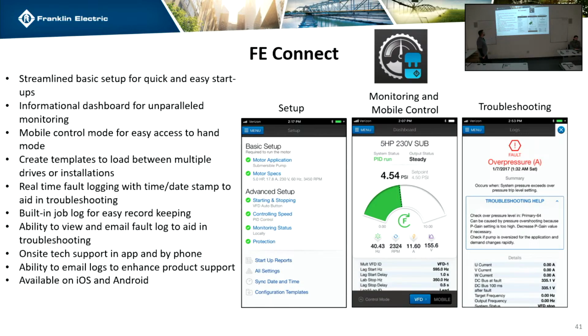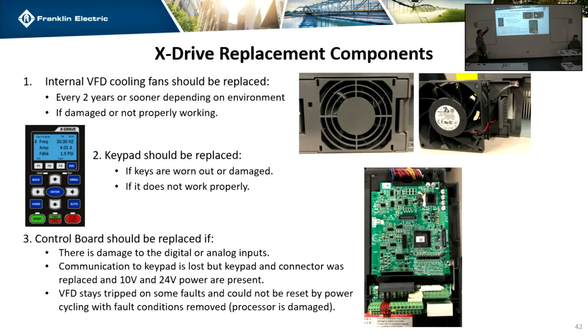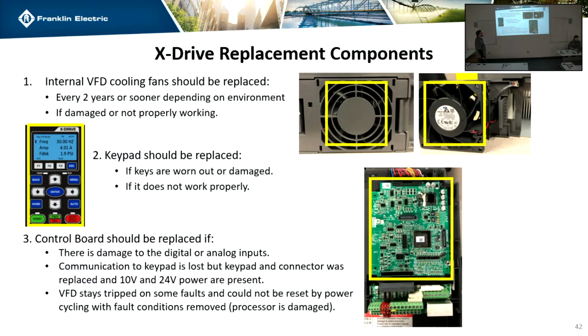Yeah, that was just a quick reference as to what the Bluetooth app is. We'll play with it in detail. The replacement components on the drive are very basic. You have a keypad, the fan, the control board. Anything that's deep inside the drive, we're not going to have a replacement for. It's a replace-the-drive situation.